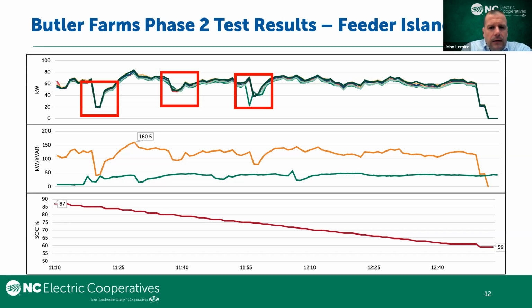The team identified this hard-coded value, and they changed it so that right before the island, the system would take a snapshot of the voltage and use that as its reference. When the control system modifications were made, as you can see towards the second half of our test, the microgrid ran and dynamically adjusted for the loads, and then it shut down and went back into grid forming when we told it to. So be careful of where you're measuring your reference and that the system is set properly.